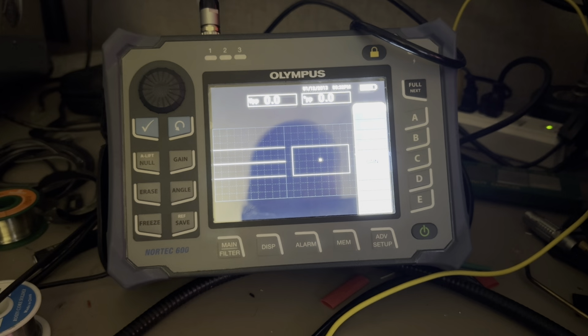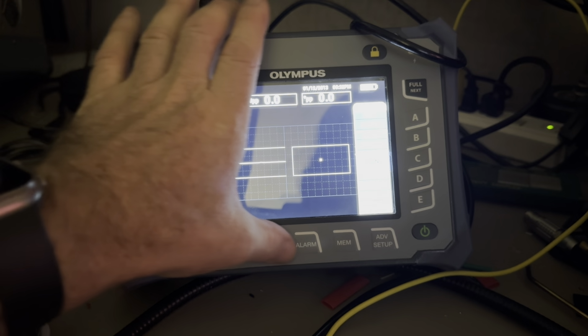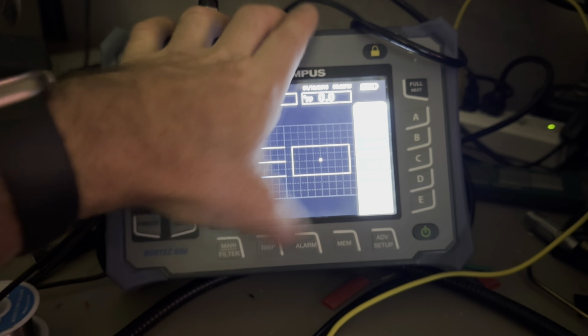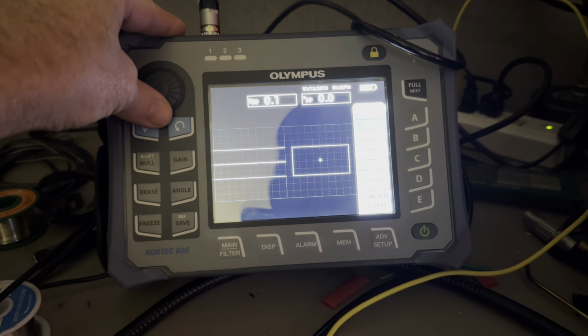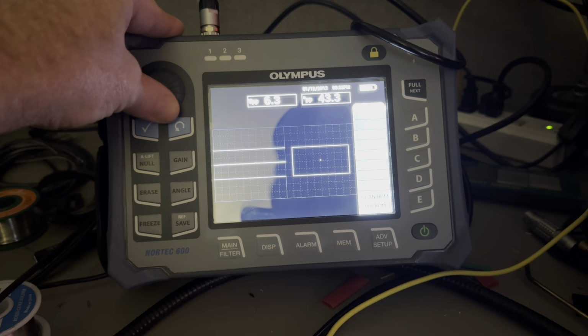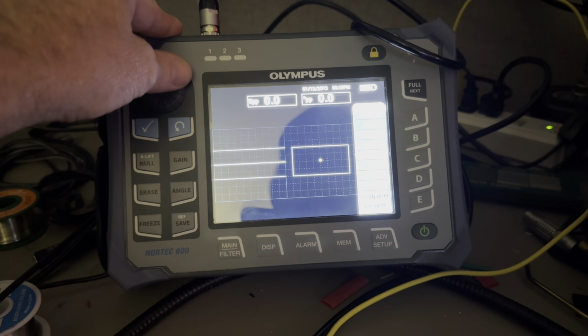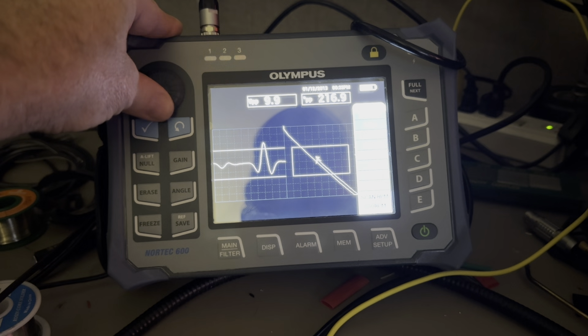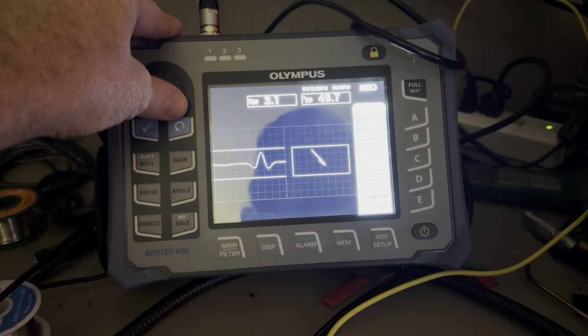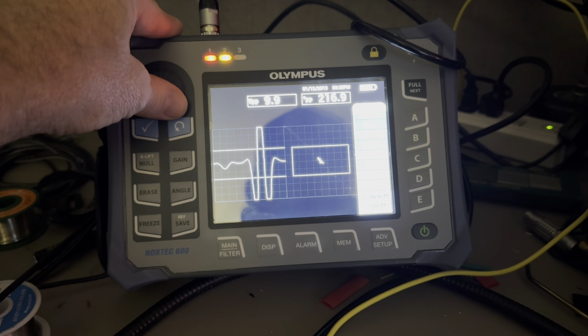So now what I want to do is turn my probe on. And one of these menus, which one is it? Could it be memory? Is it main? So scan speed. I got my Nortec 600 fixed from Olympus because my probe motor controller wasn't working quite right. So they fixed it up in a jiffy and they sent it back to me. So I'm happy to have my 600 back. So all I'm doing here is I'm holding my probe horizontal to the test material. And obviously that's going to be our probe motion just rotating over the material. So going from air to the material, 750 times a minute. So that's more than 10 times a second? It's pretty fast.